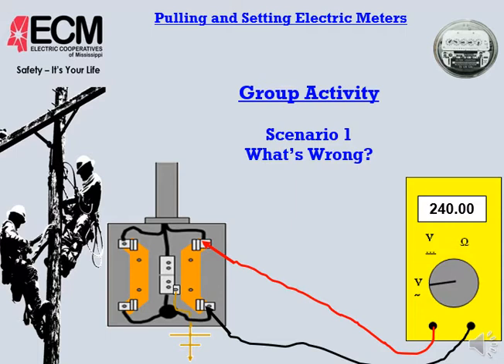So that first thing that we know, we shouldn't be getting anything in this position. But actually now we're reading 240 volts. So now we know we've got a problem. First thing we realize is we don't set the meter. Now we backtrack and figure out where the problem's coming from. We're getting another source of power, a separate leg coming from somewhere, some type of backfeed or something like that.